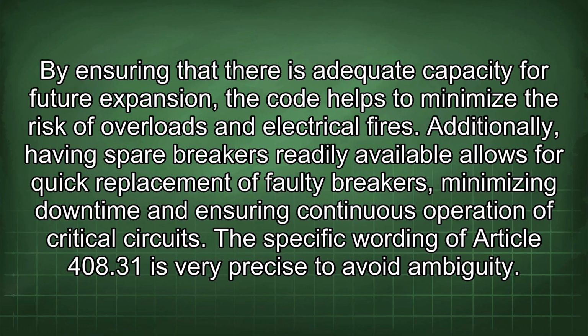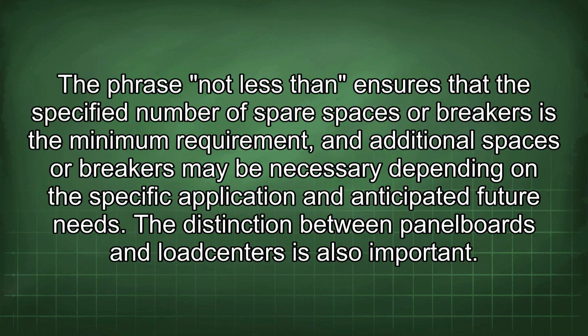The specific wording of Article 408.31 is very precise to avoid ambiguity. The phrase "not less than" ensures that the specified number of spare spaces or breakers is the minimum requirement, and additional spaces or breakers may be necessary depending on the specific application and anticipated future needs.